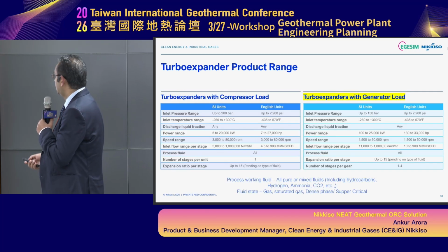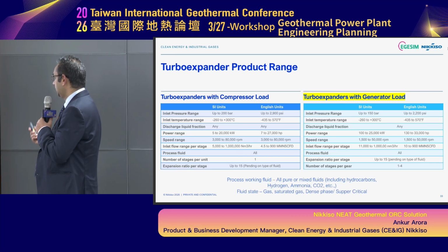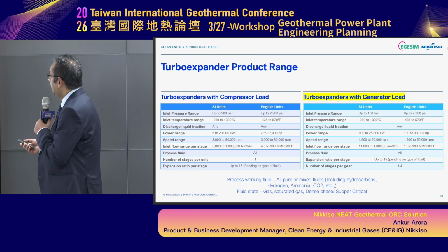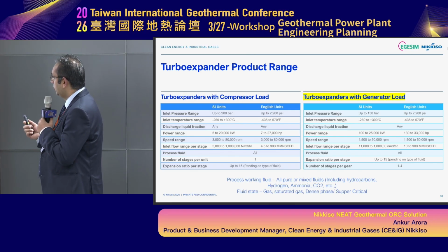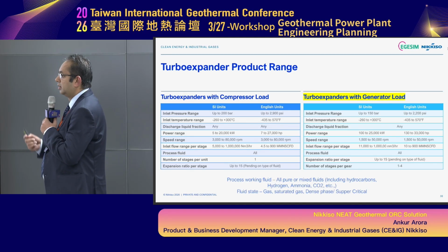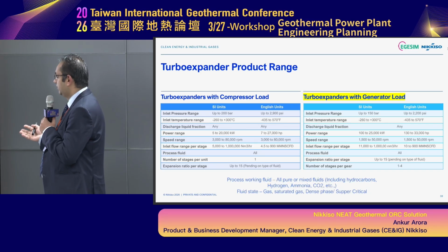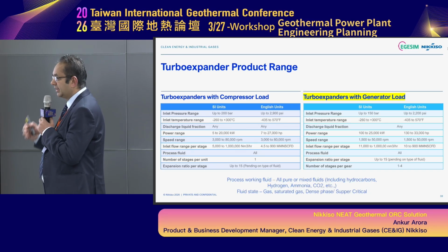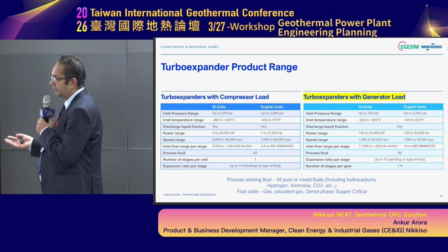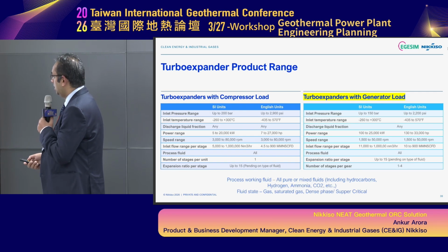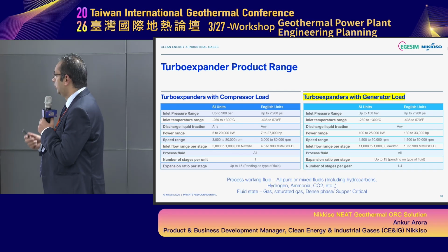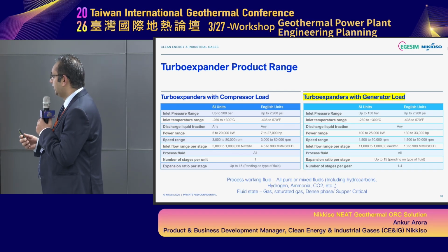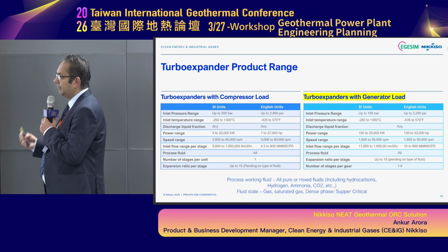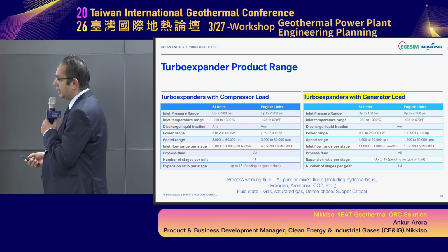Turbo expander range is limited more or less by the gearbox design, about 33 megawatts roughly. But the power range can go as small as 100 kilowatts to as large as 25 megawatts for a single train. If you double it, you can go up to 50 megawatts. Around the world, what we're seeing more and more in inquiries is redundancy coming up, so people are looking more at redundancy, and 25 megawatts is kind of the standard.